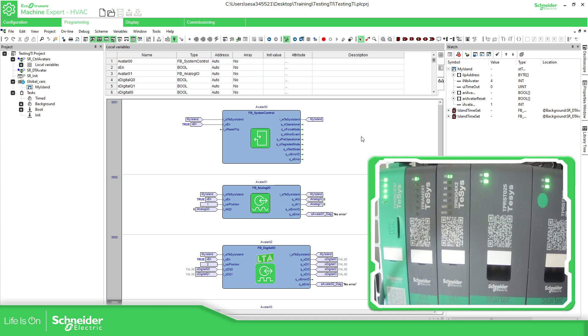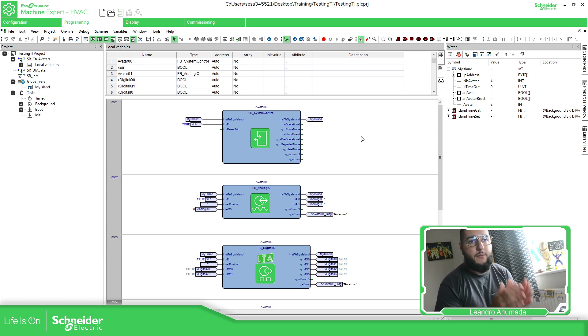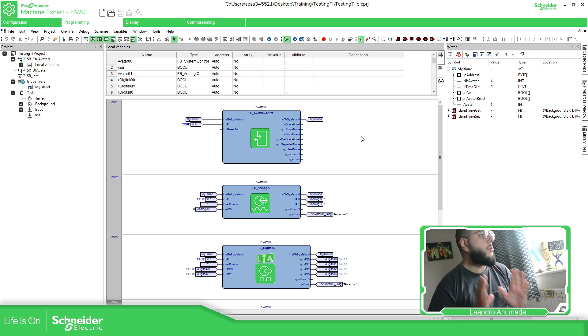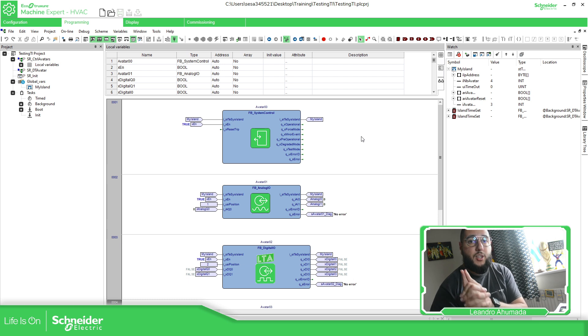On the bench I have the TeSys Island — the red one you can see first, the green one is the bus coupler. Next to it I have an analog IO, then a digital IO, and two starters. This configuration needs to be done in SoMove, and then you can download it. It's important that you match the same hardware configuration in real life with the one in software. Otherwise you'll probably get a pre-operational state and nothing will run. You can connect and ping it, but it's pre-operational so there's nothing to work with. It's also important to match the firmware and the DTM — that information is covered in the DTM release note of the TeSys Island.